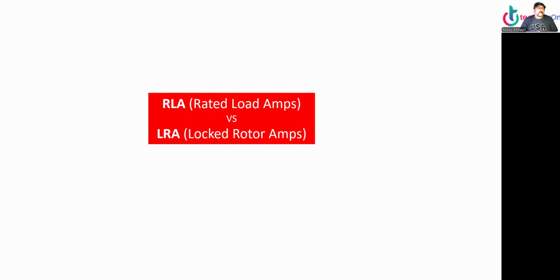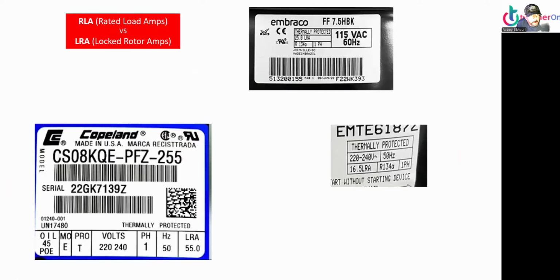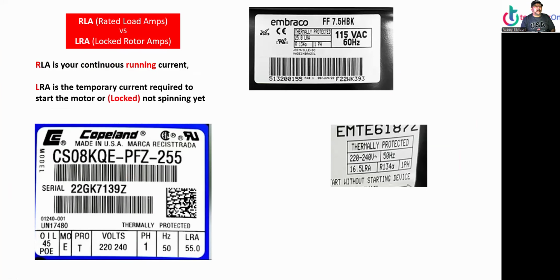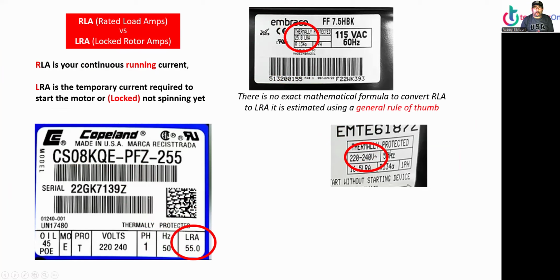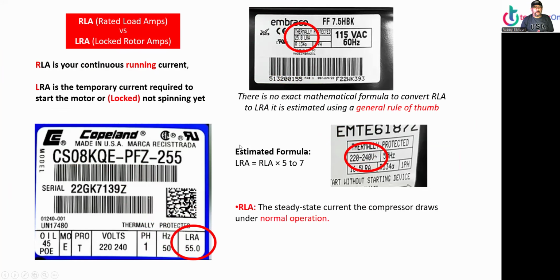Now, RLA versus LRA, rated load amp versus locked rotor amp. Rated load amp is the normal running current. Locked is a temporary amperage before it starts going. And then you can see here, it shows the amperage. It shows the locked. There is no exact formula to convert. The general rule of thumb is 5 to 7. The locked amperage is 5 to 7 times higher than the rated amperage.